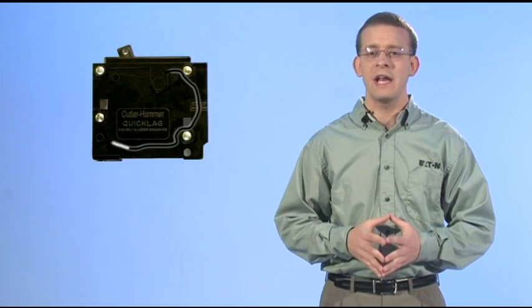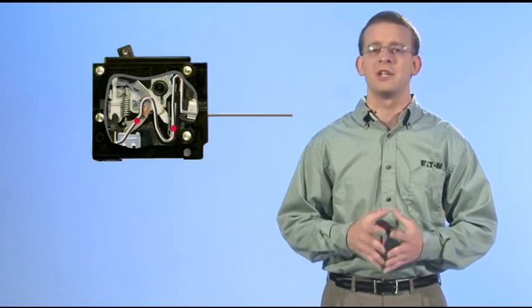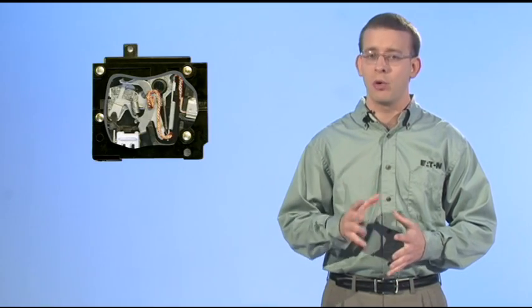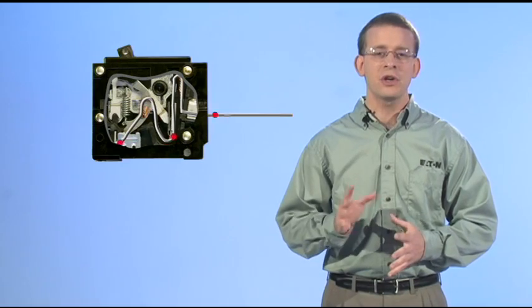It does this by way of an engineered bimetal that bends when current above its rating is applied across the circuit. It would only take a few seconds to trip the breaker if a high amount of excess current is being pulled through the circuit, but it could take several minutes if the current is just above the breaker's rating.